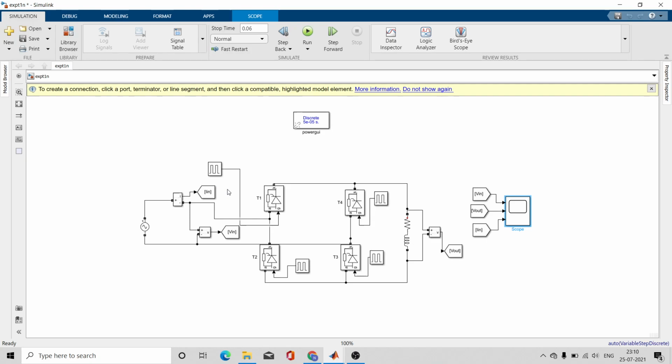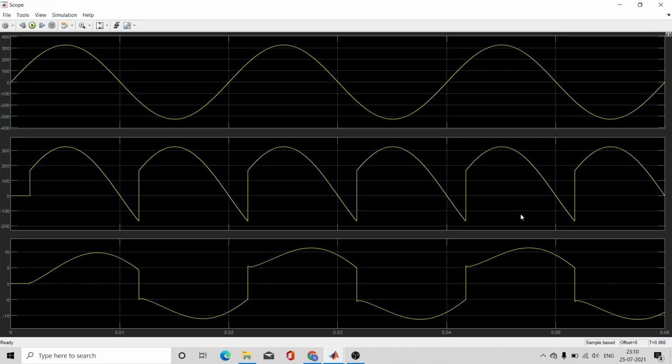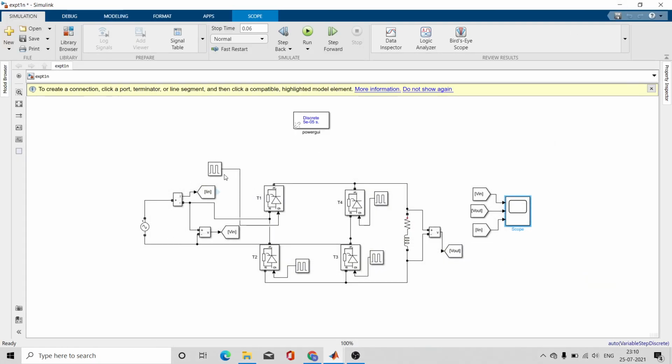Ideally in a rectifier, your input is AC and output is DC, and your rectifier should not affect the input side, but due to these controlled switches and the output that you are changing, it is not purely DC, so the overall effect will create harmonics in your input current. So remember, harmonics are first injected in your current and then they are injected in the voltages. So while studying harmonics, you must first concentrate on the current. If you are going to study the harmonics of a rectifier, then you have to see the AC side, which means the source side.